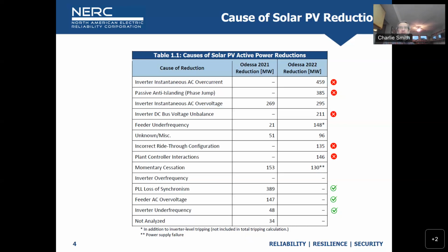Good question, thanks Harry. I think one could argue it's a PRC-19 issue, that's coordination of controls, limiters, and protections. But in a lot of these cases, the inverters are protecting themselves. They experience the trip threshold and don't have a limiter that keeps them from tripping on, say, phase jump or something like that. So they're simply tripping. Why put the onus on the TPs?